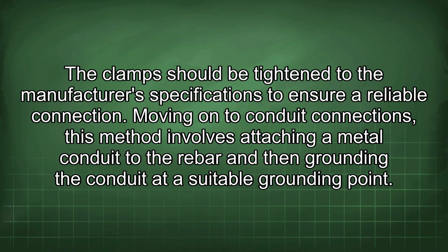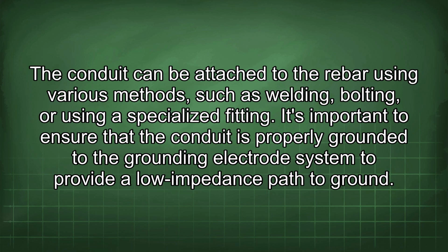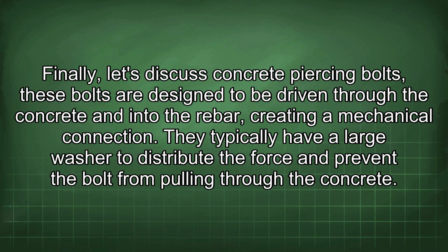Moving on to conduit connections, this method involves attaching a metal conduit to the rebar and then grounding the conduit at a suitable grounding point. The conduit can be attached to the rebar using various methods, such as welding, bolting, or using a specialized fitting. It's important to ensure that the conduit is properly grounded to the grounding electrode system to provide a low impedance path to ground. Finally, let's discuss concrete piercing bolts.